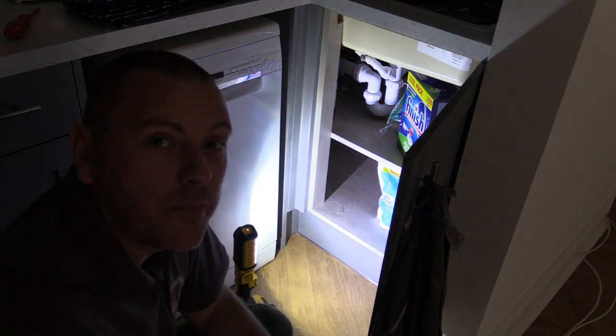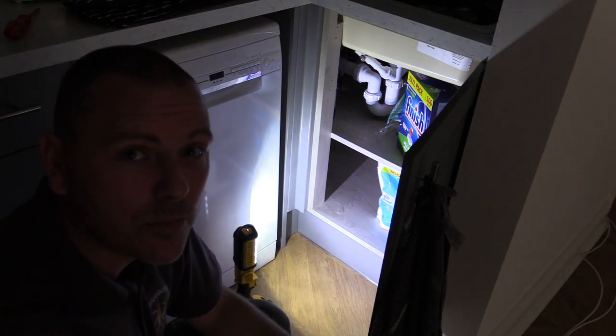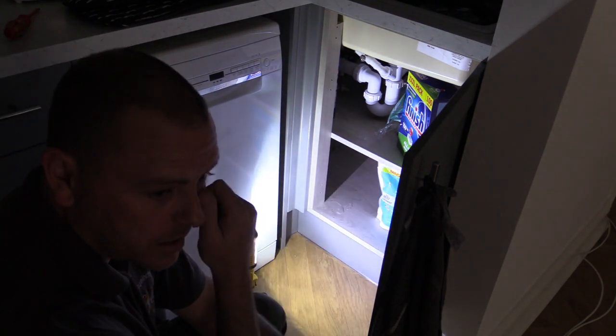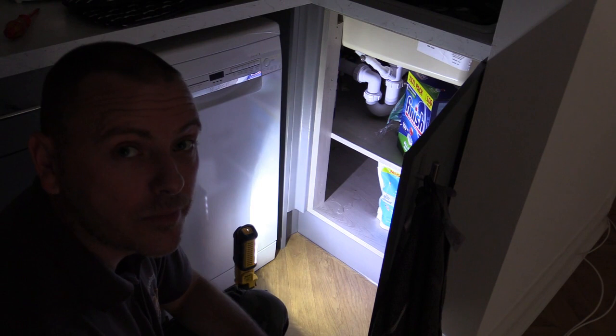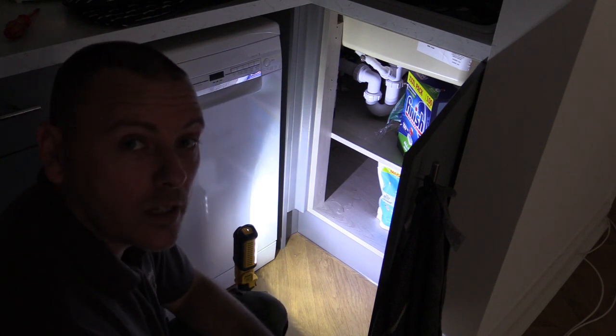So I'm going to do the same thing for the gas pipe, but I'm not going to show you that. It's exactly the same process. I'm going to take out the bonding conductors, join them, go to the gas meter, clip one of them on my R2 lead, one of them on the clamp, and do exactly the same thing again. Join me on the R1, R2s.